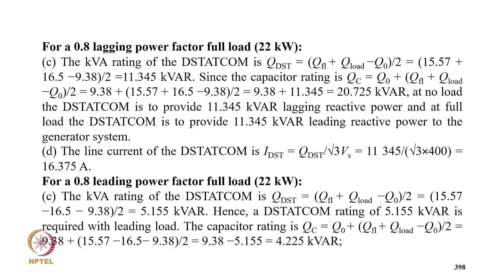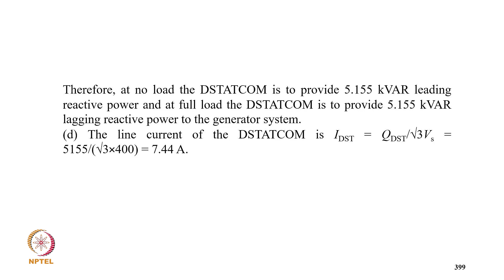so it comes to 16.39 ampere. For 0.8 leading power factor load at full load of 22 kW, the kVAr rating of the system QST equal to QFL plus QL minus Q0 by 2, that's 5.155 kVAr. So the STATCOM rating is 5.155 kVAr. The required rating of the capacitor is Q0, that is 4.225 kVAr. Therefore at no load the STATCOM will provide 5.155 kVAr leading reactive power, and at full load the STATCOM provides 5.155 kVAr lagging reactive power to the generator. So the line current of the STATCOM is QST upon root 3 VS, that comes to 7.44 ampere.